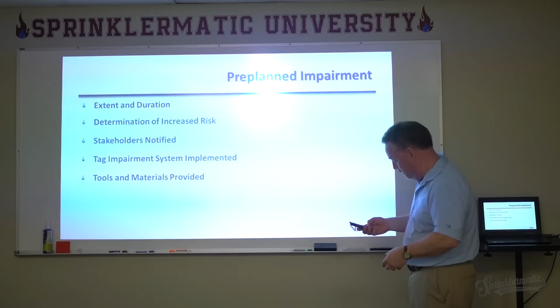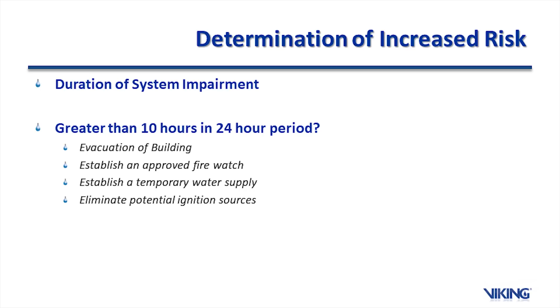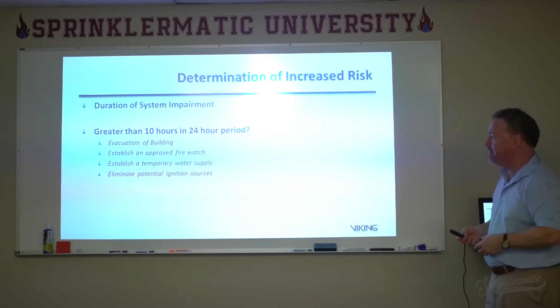The determination of the increased risk comes into play if it's greater than 10 hours in a 24-hour period. We may need to evacuate the building, establish an approved fire watch, maybe a temporary water supply depending on what the impairment is, and eliminate potential ignition sources. These are all part of that evaluation when we have an increased risk. And then restoring everything back is simply reversing it back out, okay? Taking the verification of operation, do the necessary inspections and tests, stakeholders are informed, and the impairment tags are all removed. So it's kind of a lockout, tagout, if you're familiar with that with electrical equipment. So you tag in, you tag out, and you document all that.